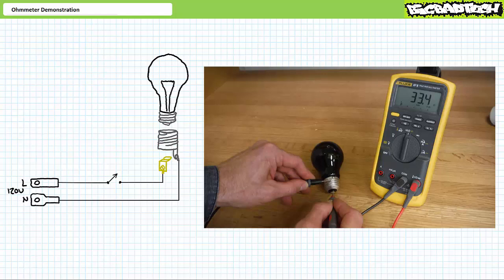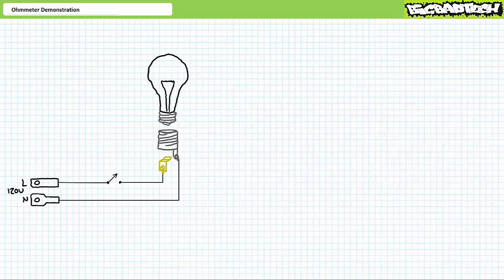Something else is. Either the source, the switch, or the means of distribution. The source is immediately ruled out from consideration since other electrical devices plugged into the same outlet function. The problem therefore exists in the switch, or the distribution system, none of which is immediately visible to the naked eye. Time to use the ohmmeter. Our job is to find the unintentional open somewhere inside the path from the functioning source to the functioning bulb.